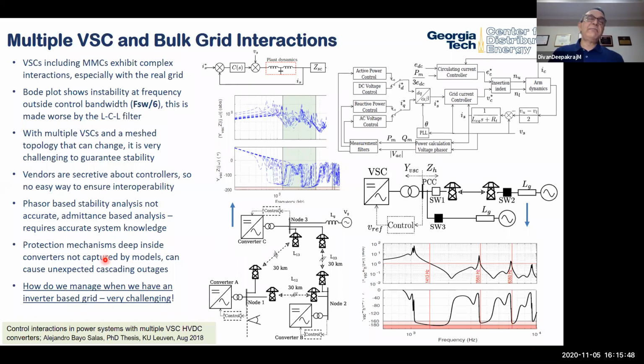On top of that, we have protection mechanisms deep inside inverters that are not captured by the models. We have seen several examples of near cascading outages triggered by these inverter trips, and these are changing very, very fast. The utility is not very used to or accustomed to having change occur so quickly. So we can start seeing the scope of the problem that we are getting towards.